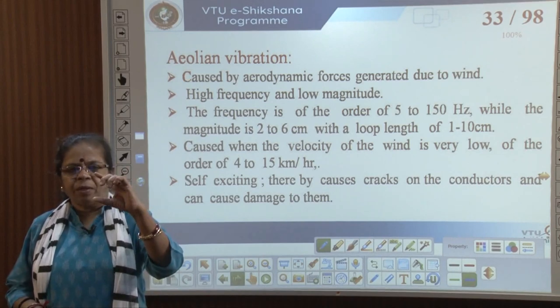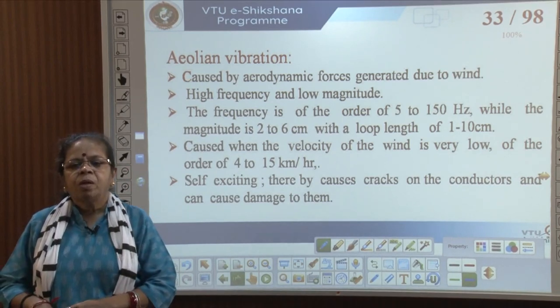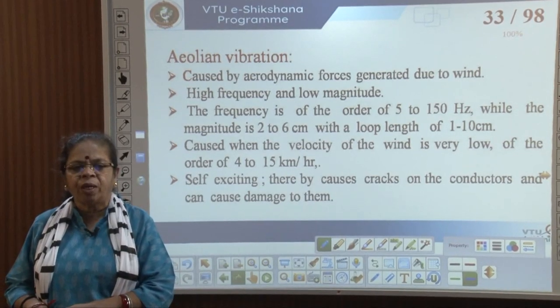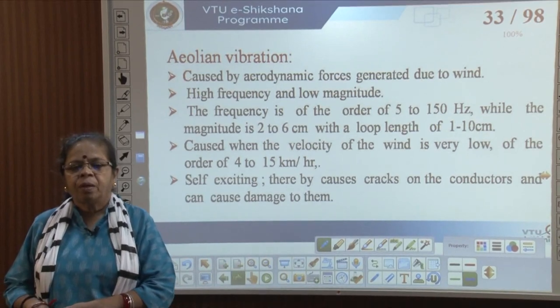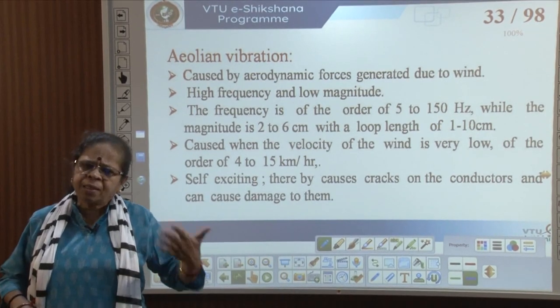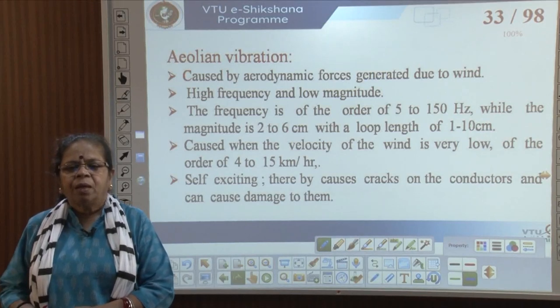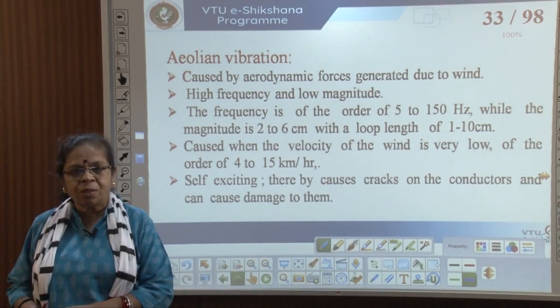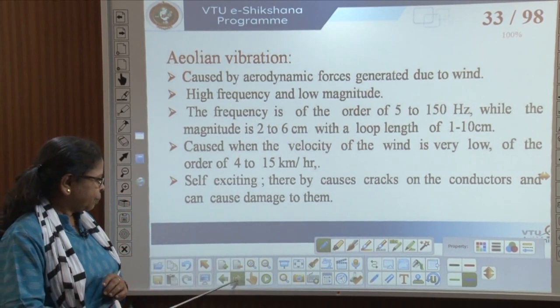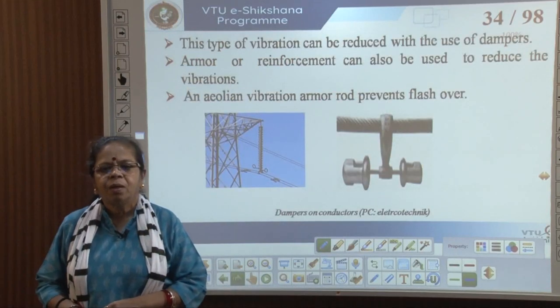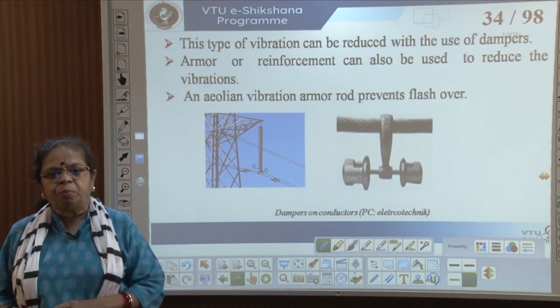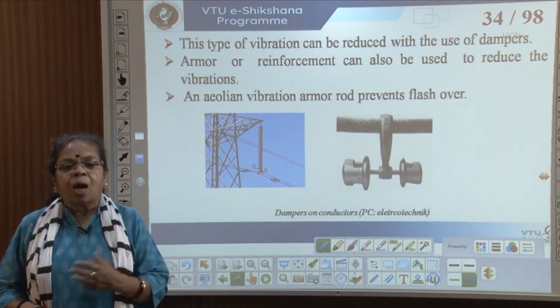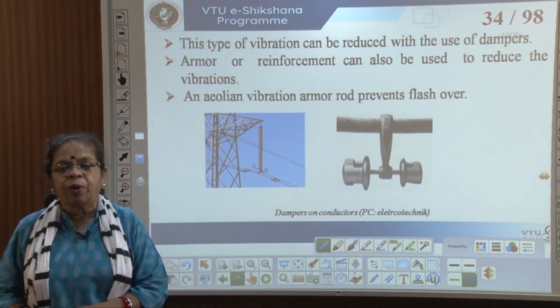2 to 6 centimeters is not a large magnitude. Aeolian vibrations are generally caused when the velocity of wind is low — around 4 to 15 kilometers per hour. They are self-exciting, picking up in the presence of wind, and thereby cause cracks on the conductors and damage to them.